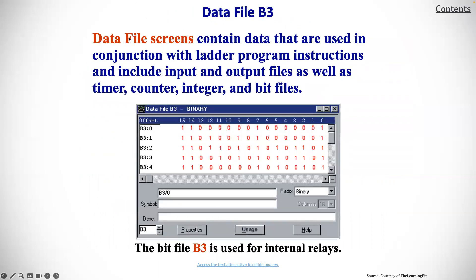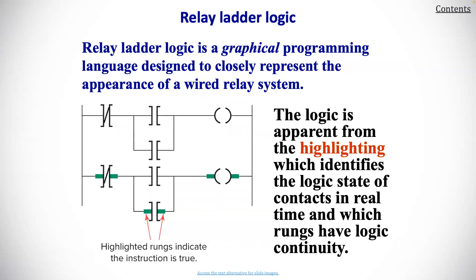The data files screens contain the data that are used in conjunction with the ladder program instructions and include input and output files as well as timer, counter, integer, and bit files. The relay ladder logic is a graphical programming language designed to closely represent the appearance of a wired relay system. The logic is apparent from the highlighting which identifies the logic state of the contact in real time and which rungs have logic continuity.